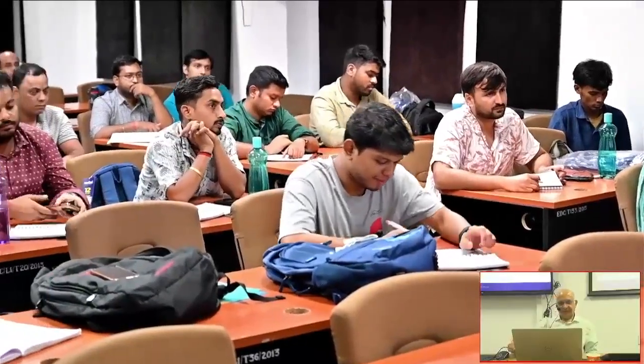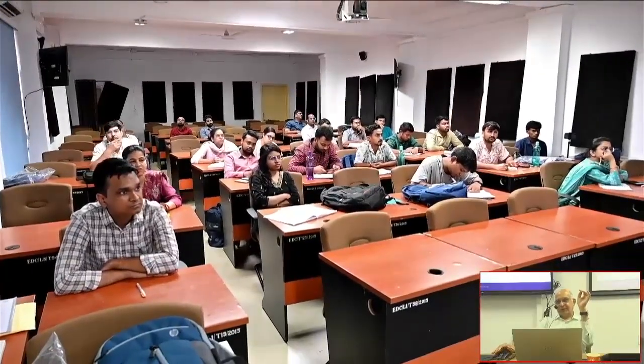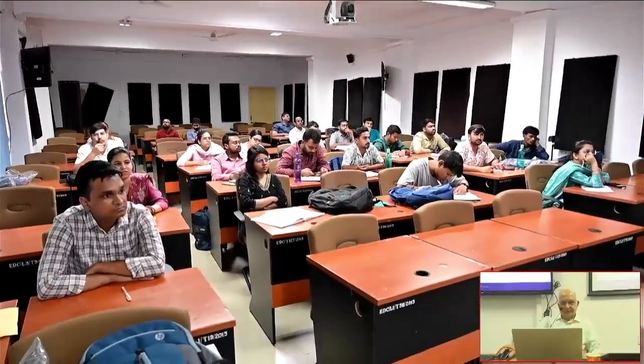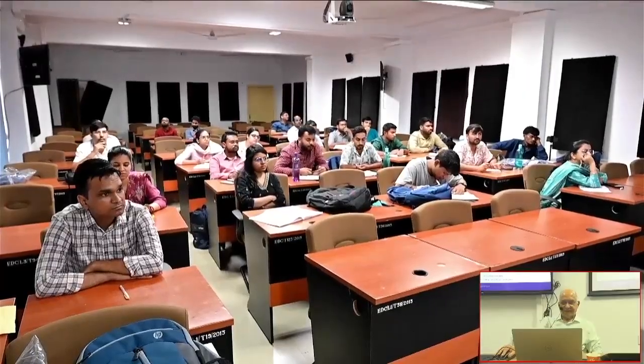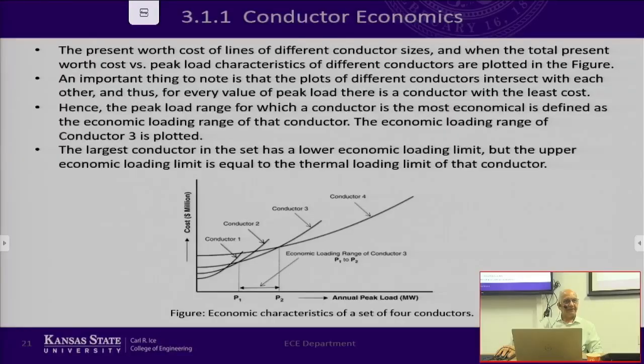So what we define is the reach at different values. The first thing we call is the thermal reach. Thermal reach basically means that you want to load the conductor to the maximum value, which, if you look at the previous graph, is where conductor number 4 can go all the way up to here, the maximum load that it can carry. At the thermal limit, whatever the P happens to be, you calculate the reach based on that, and we call that the thermal reach.